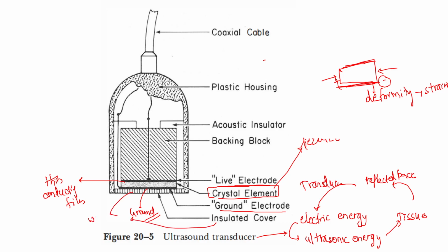The insulated cover is actually a watertight electrical insulator placed between the ground and the patient, so that the current will not pass into the patient. Then the inside electrode, the live electrode, abuts the backing block. This whole part is the backing block, so this inside or live electrode will abut the backing block. The backing block will absorb the sound waves transmitted back into the transducer.